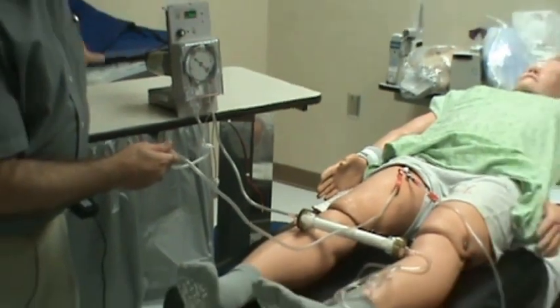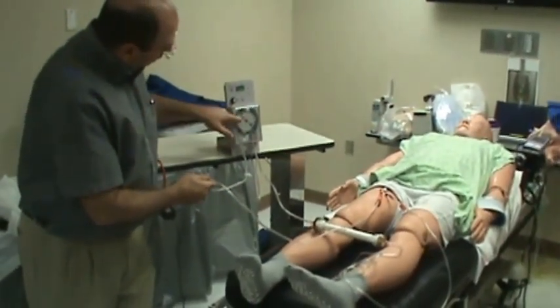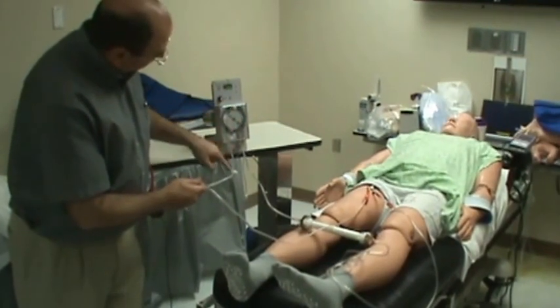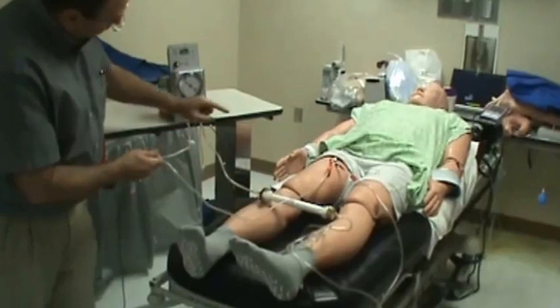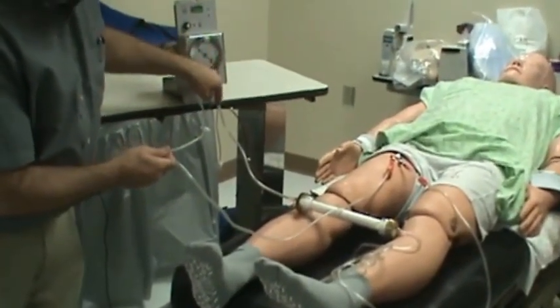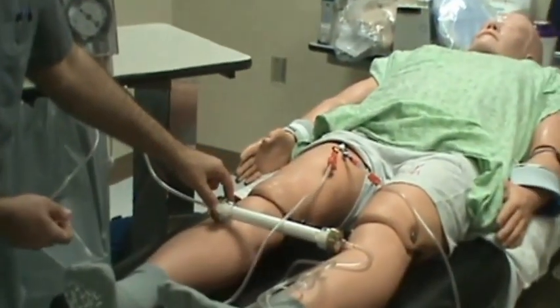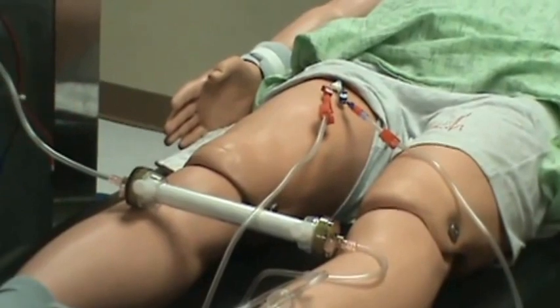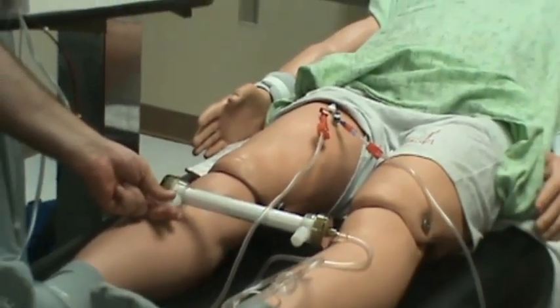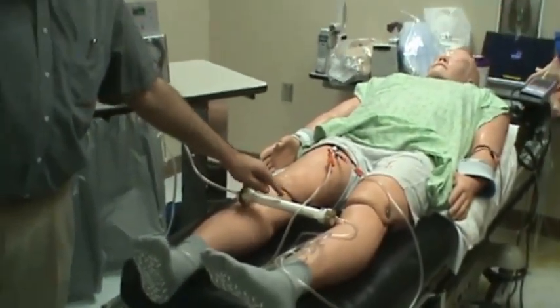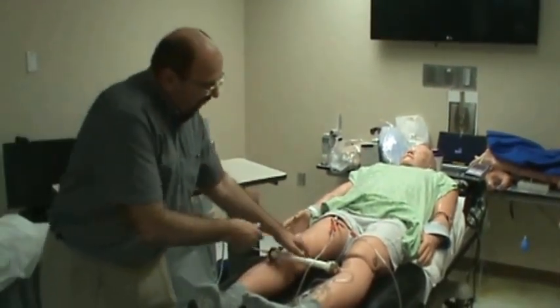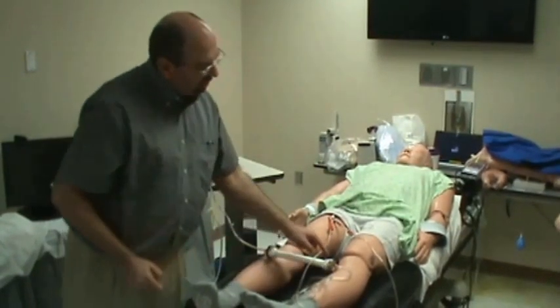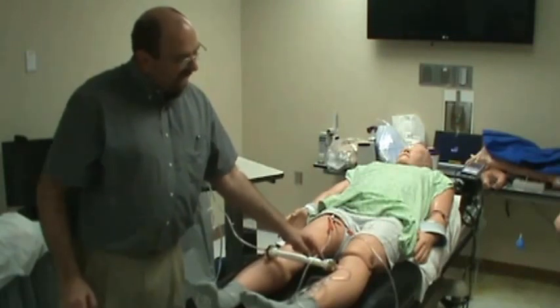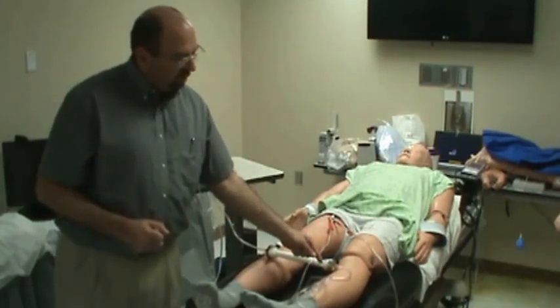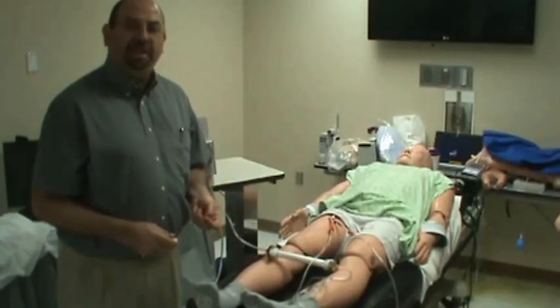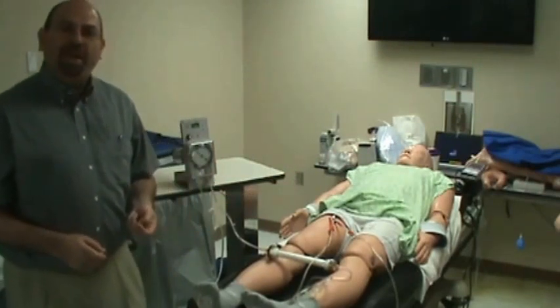into the pump. And if you look, the pump will turn clockwise. So the blood continues to be vacuumed out through the tubing into this large tube that goes into the filter. The proximal end of the filter is actually sealed. Think about it that these fibers would have a positive hydrostatic pressure. So if you open the second portion of the dialysate side of the hemofilter, fluid is going to come out, and that is what ultrafiltration is, and it will pull with it a lot of the waste products.